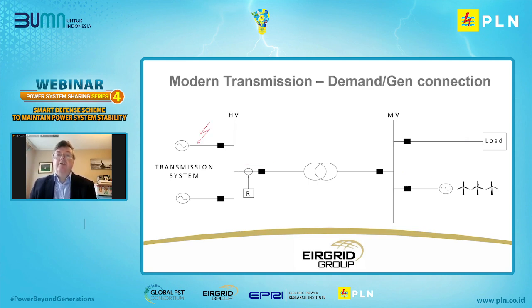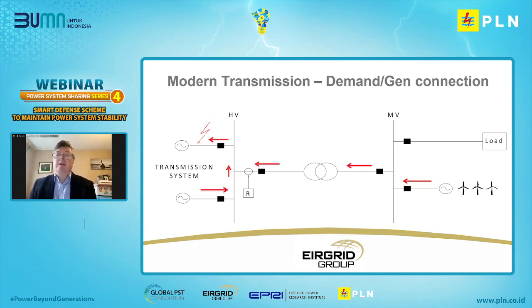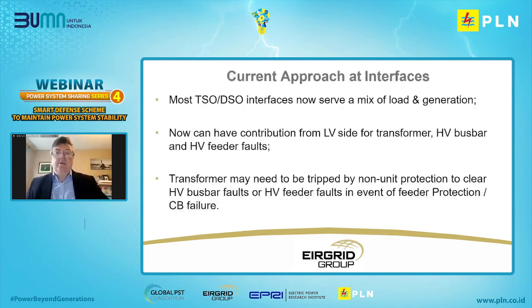Okay, so now we're showing a fault on the transmission system itself. Advance one more, please. Now we've got contributions coming from the distribution system, which we didn't have in the past, and so our protection was not set up to deal with this. Our current approach is that, as the TSO-DSO interface serves a mix of generation and load, we could have contributions from the LV side through HV busbar faults and HV feeder faults. So the transformer may need to be tripped by non-unit type protection to clear HV busbar faults or HV feeder faults in the event of feeder protection or circuit breaker failure. Move on to the next slide, please.